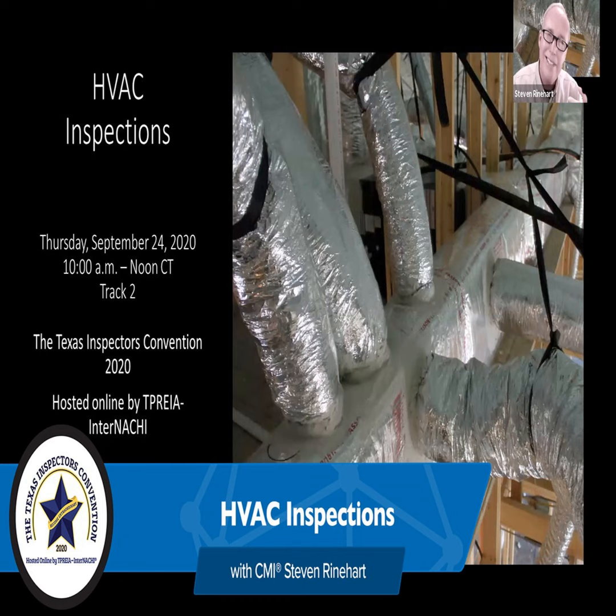But if I don't get 20, 30 degrees of heat on a heat strip, I might put in there, okay, it worked, but it wasn't what I was expecting.